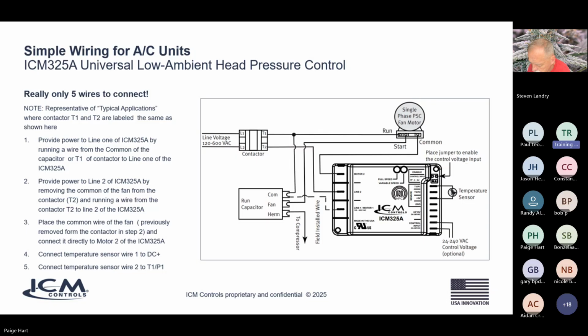Now, you'll still have that wire from the motor in your hand. That's just going to go to motor 2. So it's literally just 3 wires there. You've got the one side of power to the motor, which I'm calling the common of the motor, that's going to motor 2. You've got T2, which is one side of your main power from the contactor going to line 2. And T1 coming from the common of the capacitor going to line 1 of the ICM.